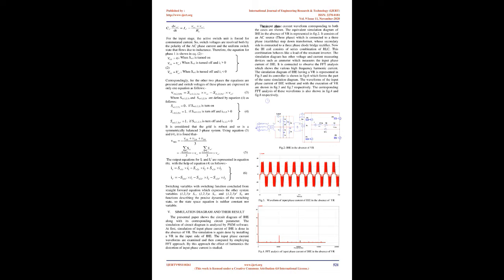3. Harmonic elimination by using Vienna rectifier, VR. The Vienna rectifier is more efficient nowadays, due to its applications in improving power quality. The Vienna rectifier has a unidirectional nature, and for this the VR defends the induction heating system from the high-frequency harmonics. Over the past few decades, large industries have needed various power converters to nullify their losses. For this reason they found that the Vienna rectifier, VR, is the most advisable and profitable consideration due to its power quality improvement and greater reliability.